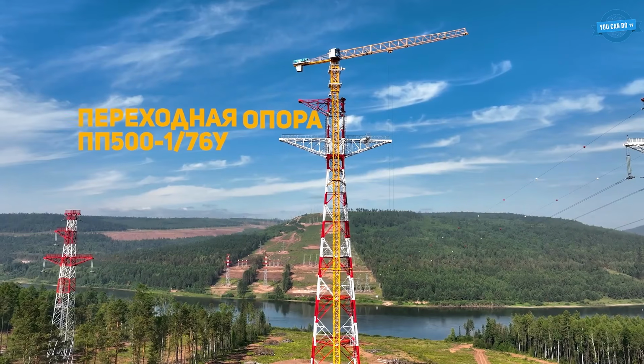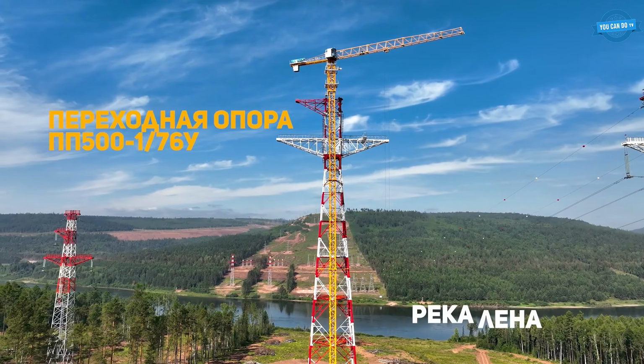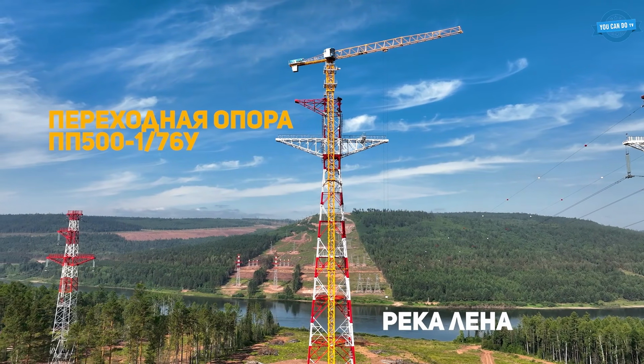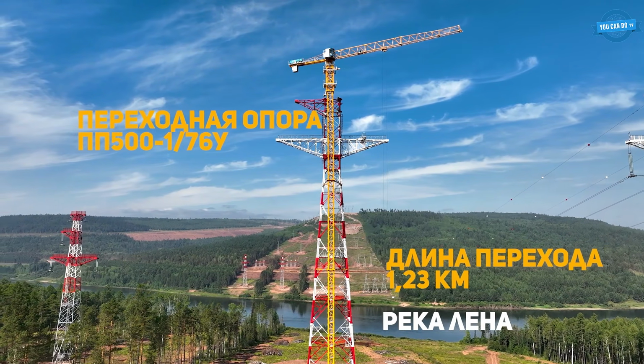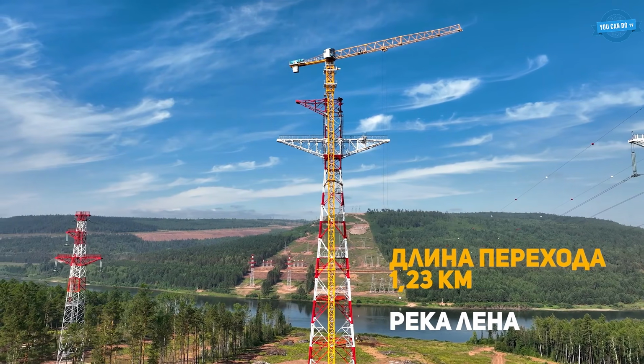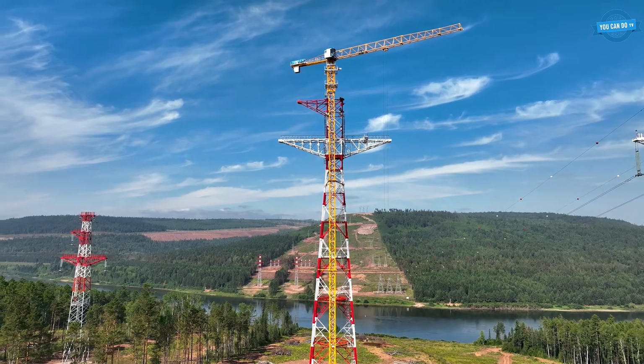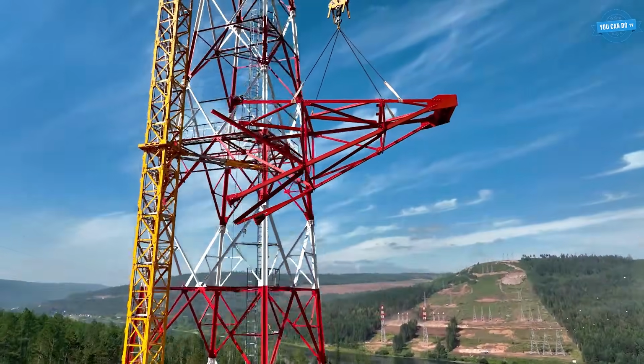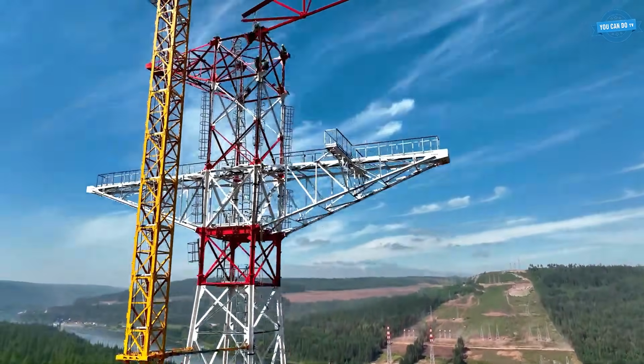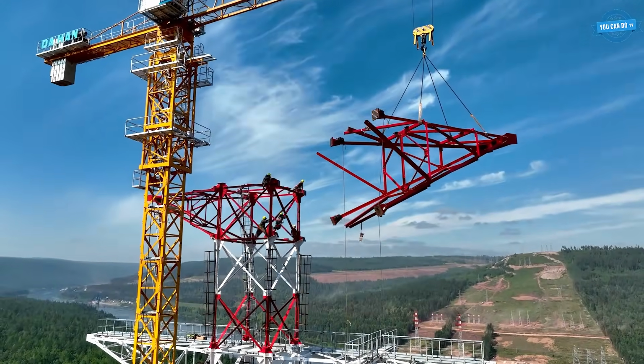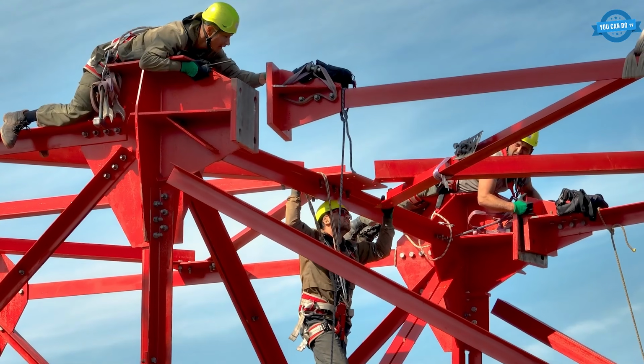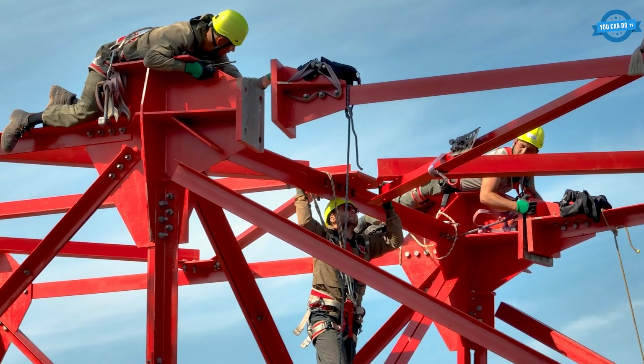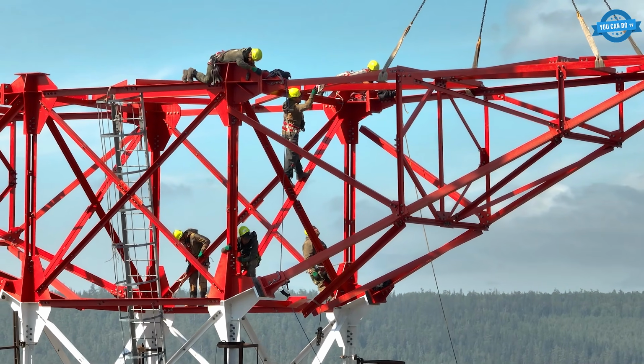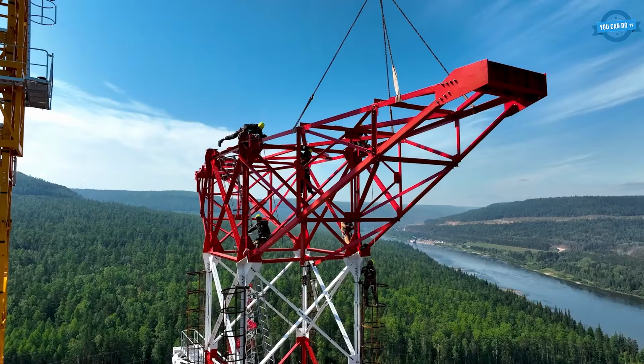At 88 meters tall and 152.6 tons, the second river crossing tower at the Lena gets built by tower crane reaching 95 meters up. An 11-meter, 2.9-ton crossarm lifts to the top and gets bolted on. The work platform follows. 2 towers stand symmetrically across the river, ready for 500 kilovolt conductor stringing.